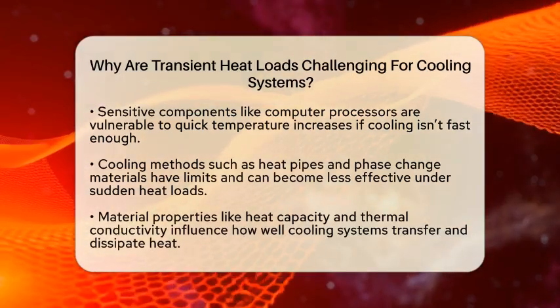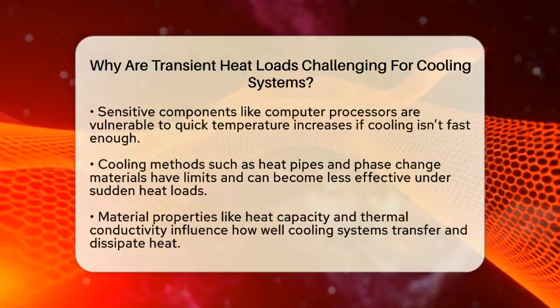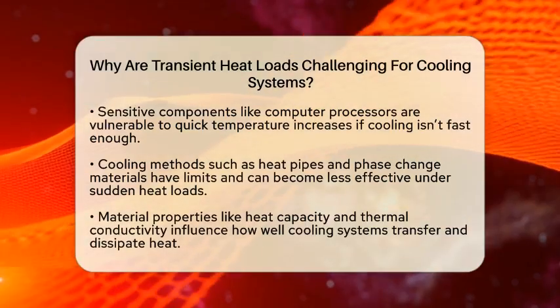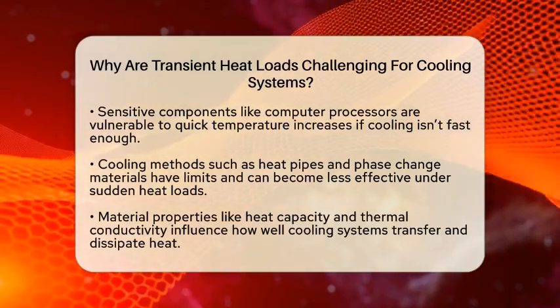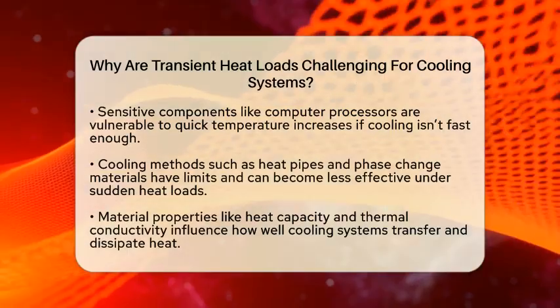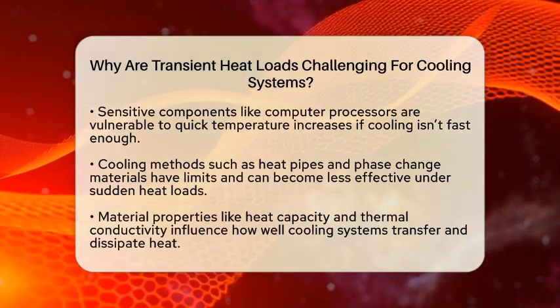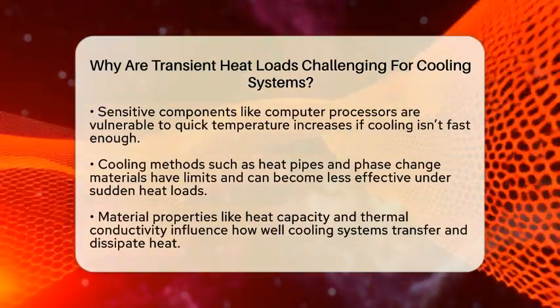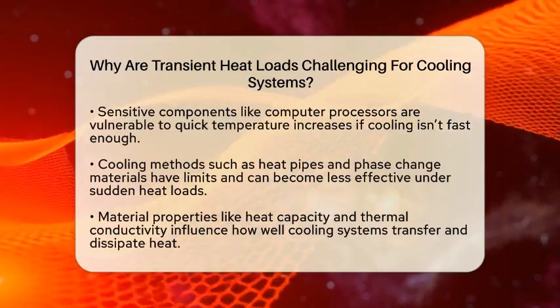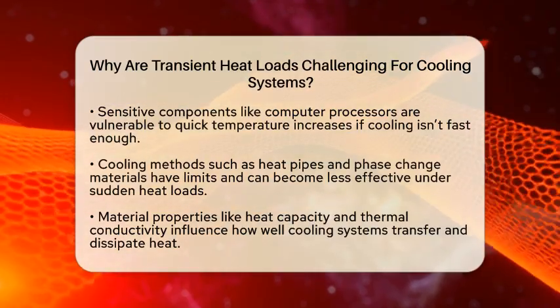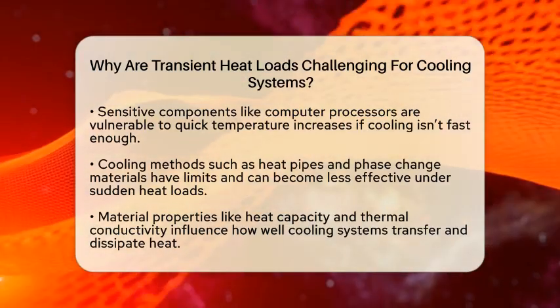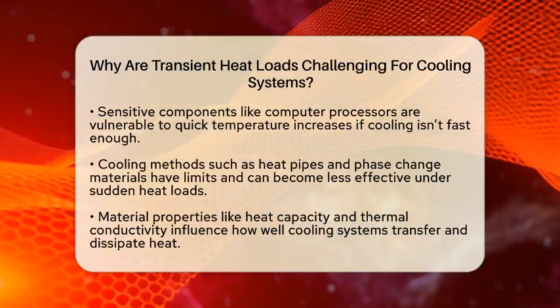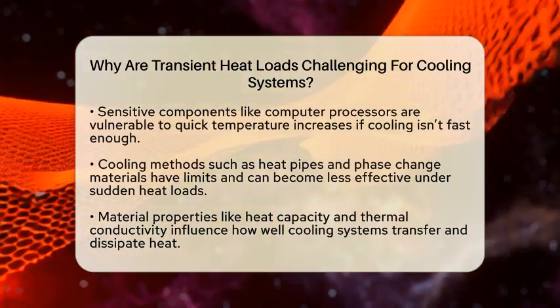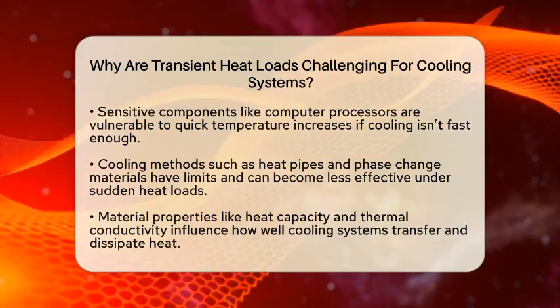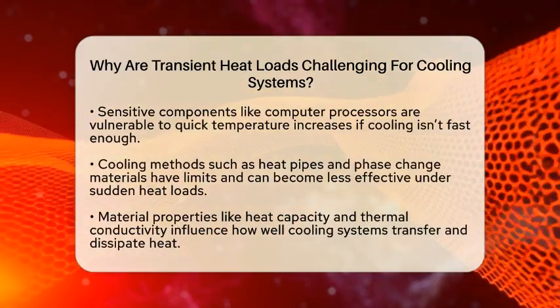Phase change materials, which absorb heat during melting, can act as buffers but only if designed properly. Their effectiveness depends on surface area, thermal conductivity, and melting temperature. Materials used in cooling systems also matter. They have specific heat capacities and conductivities. If a material cannot transfer heat fast enough, it becomes a bottleneck. Proper design involves balancing these properties to handle both steady and transient loads.